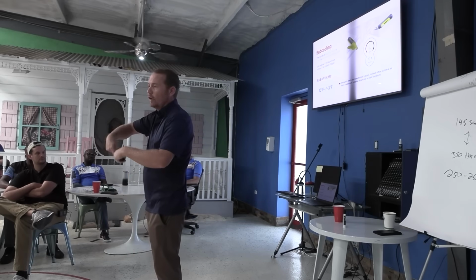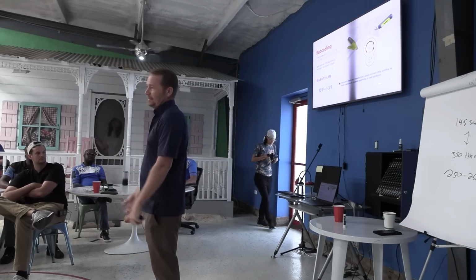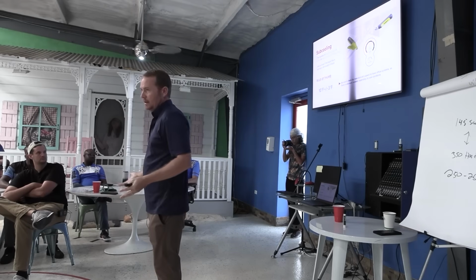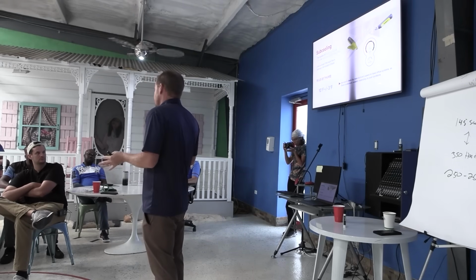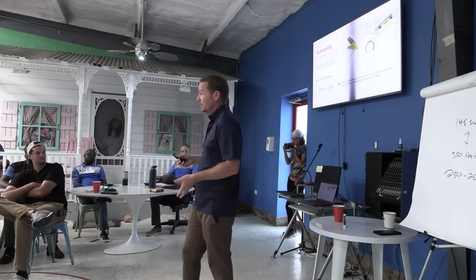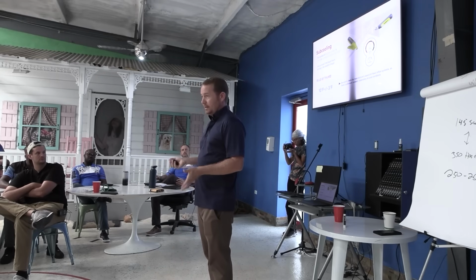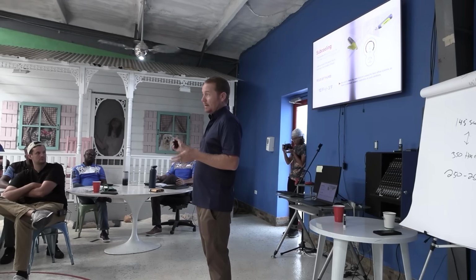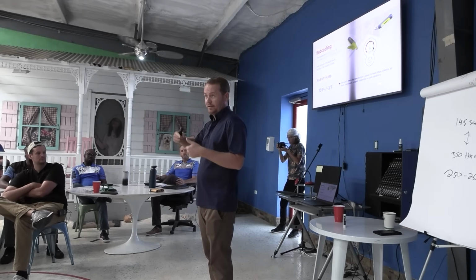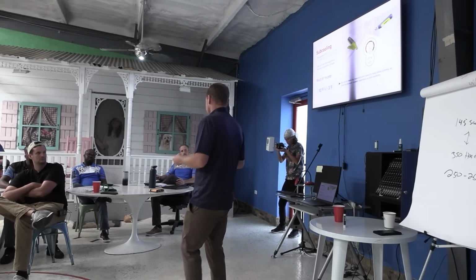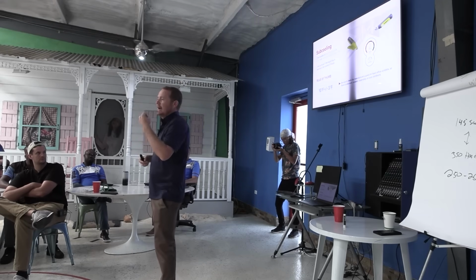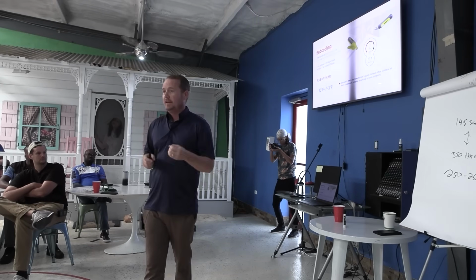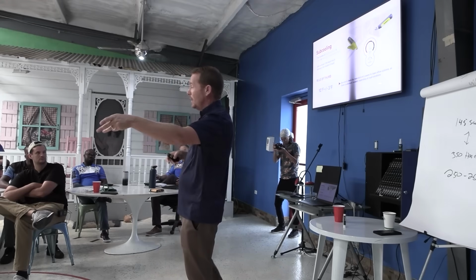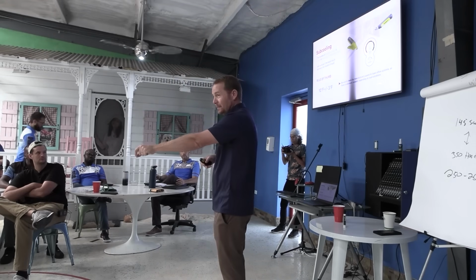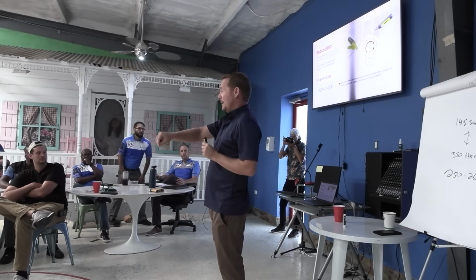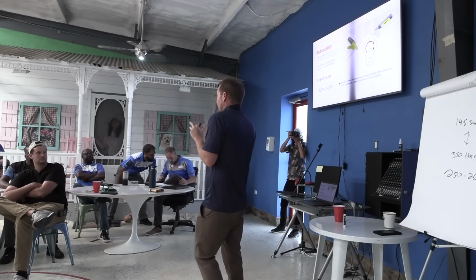So you can do the hose on it, give it 6 hours, 24 hours, whatever, give it time. Odds are it's going to reset. Now sometimes it's an embarrassing conversation to have with the client, because it's like, look, it's not resetting on me right now, we're going to have to come back, but I'm going to run these other calls and then come back and see. But don't just condemn the compressor, because that compressor 99% of the time will end up resetting, and then you can find the cause of what caused it in the first place. Because if you replace that compressor, the problem that caused that to happen to the compressor is still there, and you don't even know what it is.